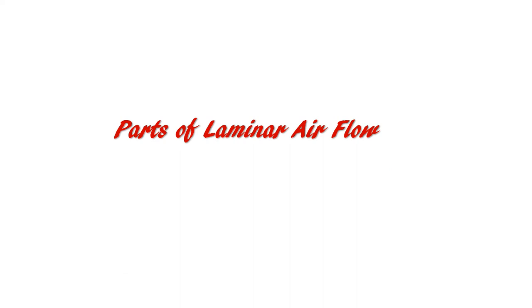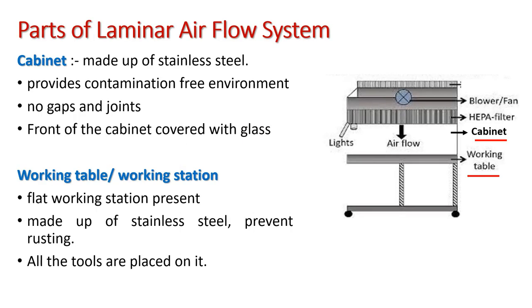Parts of laminar airflow. The first part is the cabinet. This enclosed cabinet is made up of stainless steel; it provides a contamination-free environment. Inside the cabinet there are no gaps and joints, which prevent accumulation of spores. The front of this cabinet is covered with a glass shield which can be opened completely or partially, helping the user to work inside.